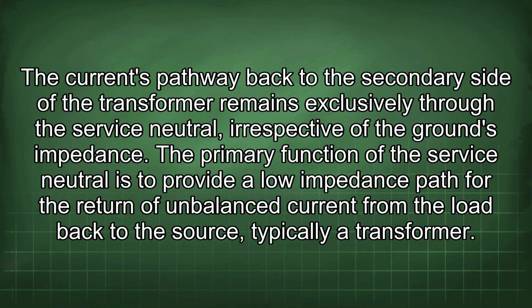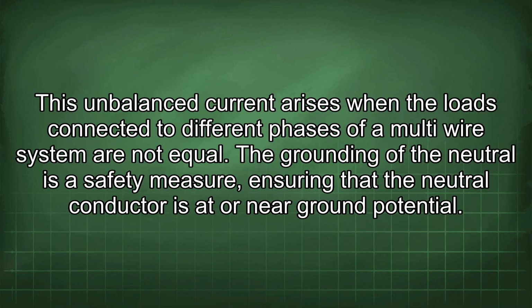The current's pathway back to the secondary side of the transformer remains exclusively through the service neutral, irrespective of the ground's impedance. The primary function of the service neutral is to provide a low impedance path for the return of unbalanced current from the load back to the source, typically a transformer. This unbalanced current arises when the loads connected to different phases of a multi-wire system are not equal.